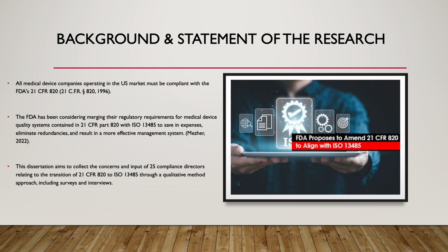Last year, the FDA announced they intend to harmonize and modernize their quality system regulation for medical devices. The revision will supplant the existing requirements with the specifications of an international consensus standard for medical device manufacturers, known as ISO 13485.